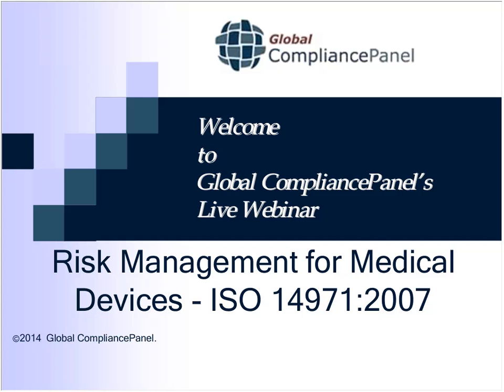All right, so let's look at the current status of ISO 14971 2007. It is the second edition, and it replaces the previous edition and an amendment. It was published on March 1st, 2007, and it comes from ISO. So this is the international standard. This is not the standard that is used in any given country or region. The standards in countries and regions are based upon this standard, but this is the international standard. It's managed by ISO TC 210, and they deal with a lot of quality aspects of medical devices. So that's where the expertise lies.